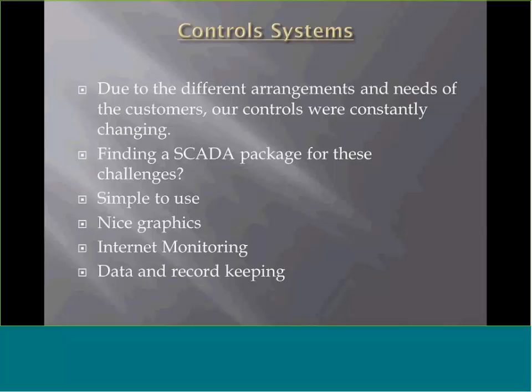It's awesome. Some of the other things that were very important and a must were the monitoring, the internet monitoring, the long distance monitoring. Like I said, that alone has saved customers lots of money from buying me a plane ticket and having to fly down there. And you'll be surprised. You get online and all of a sudden you see that it's just a bad temperature probe or a bad float or some kind of bad sensor.